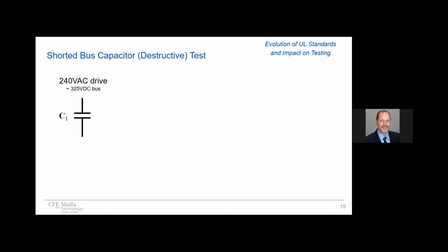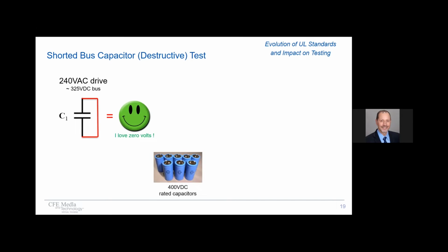So let's look at the 240 volt class of drives and the 480 volt class of drives separately. On a 240 volt class of drive, the rectified value, in other words, the bus voltage, is around 325 volts. And generally we have capacitors in parallel, many of them, but not in series. And we use 400 volt capacitors in that circuit. So that 325 volt bus is no problem for a 400 volt capacitor. And in fact, when we simulate a short across it, the capacitor likes it even more. It's very happy. So we're taking it from an average stress down to zero stress. And of course, there's no issue there. And as I mentioned, those are 400 volt rated capacitors that are used.